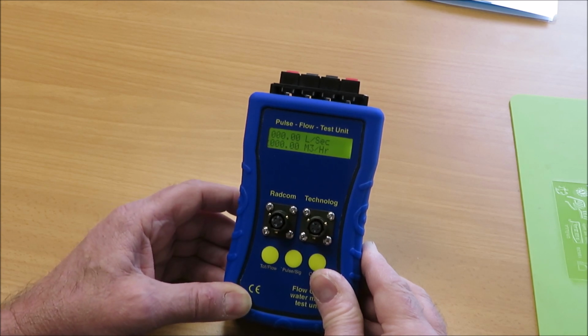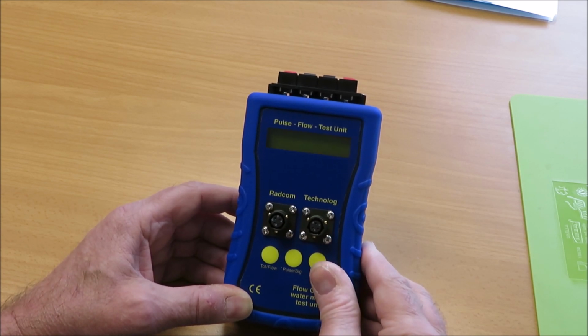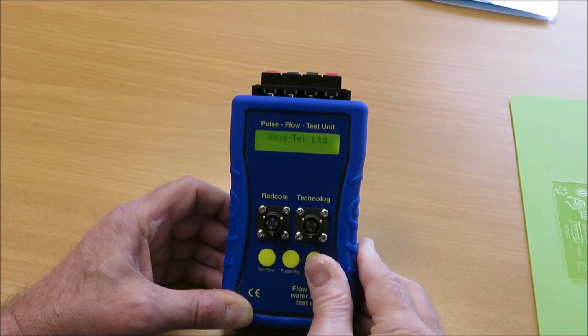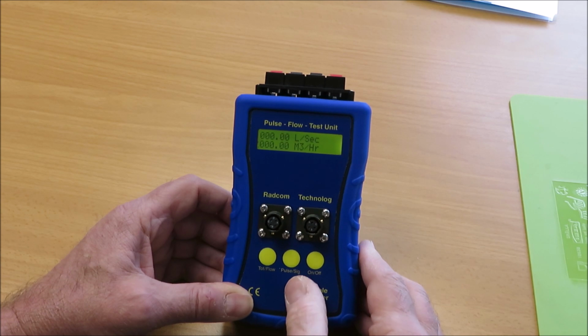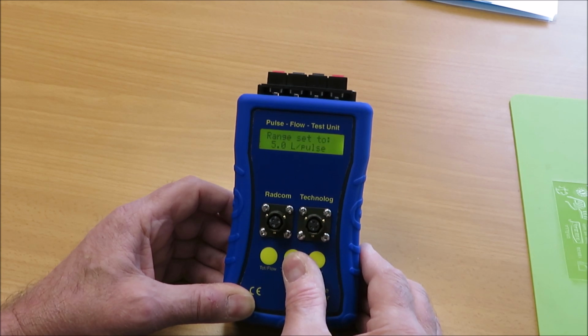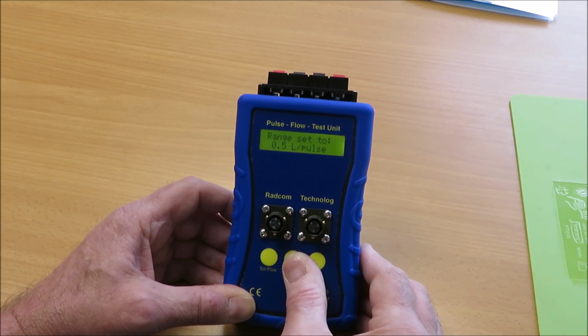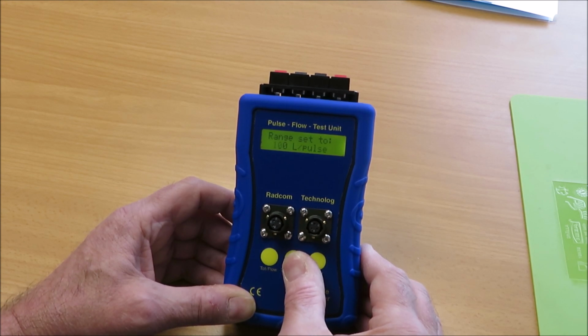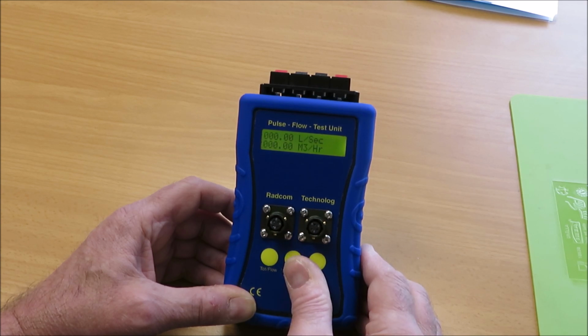Now if when switching the unit on you notice that the range of 1 litre a pulse is incorrect, or you wish to change it, you're just not looking to see if you're getting pulses, you can press the middle button which says pulses significance. The first press steps it through. So you can see you can go from half a litre a pulse to 1 litre to 5 litres to 10 litres, 100 litres and 1000 litres a pulse. If I put it on half a litre, that's a typical T-probe setting.